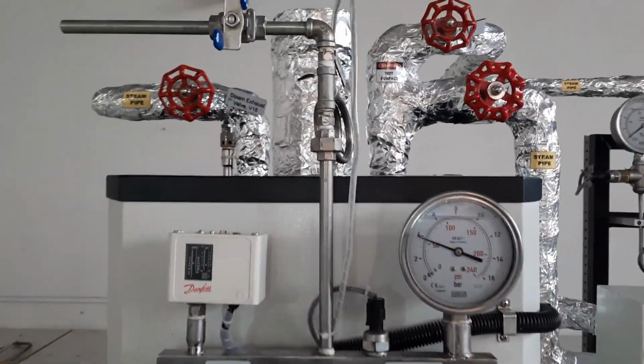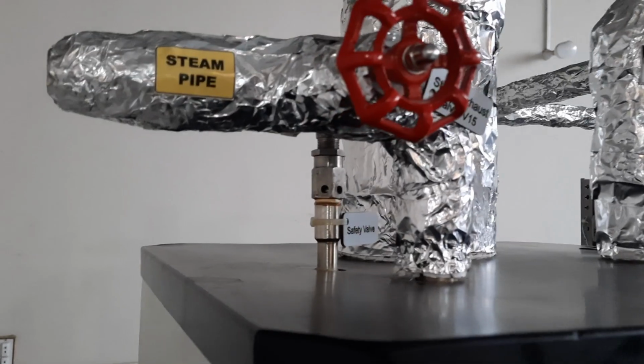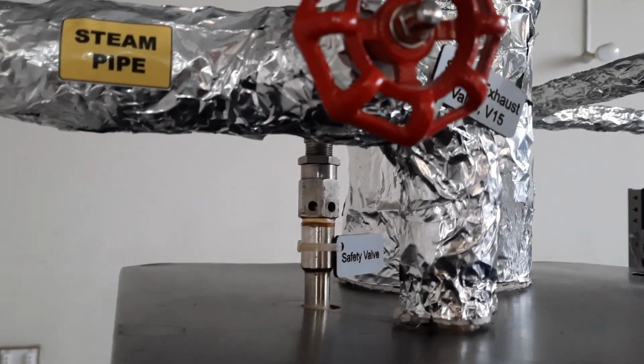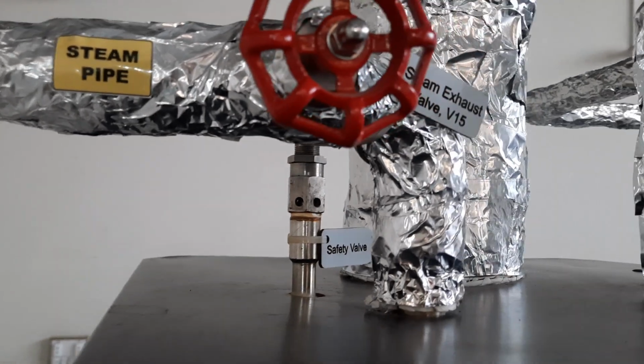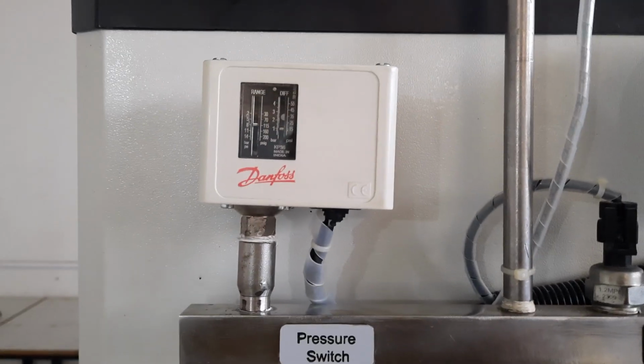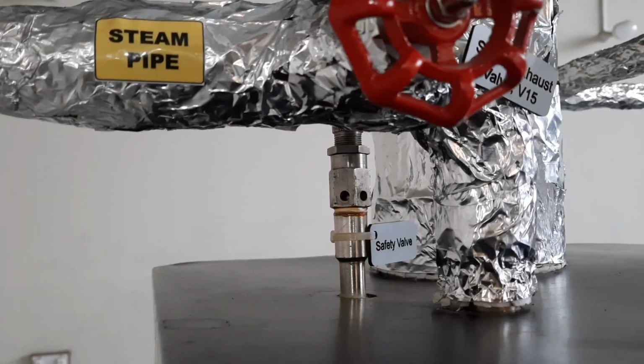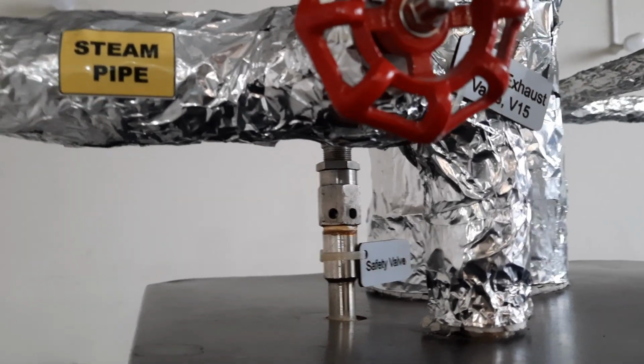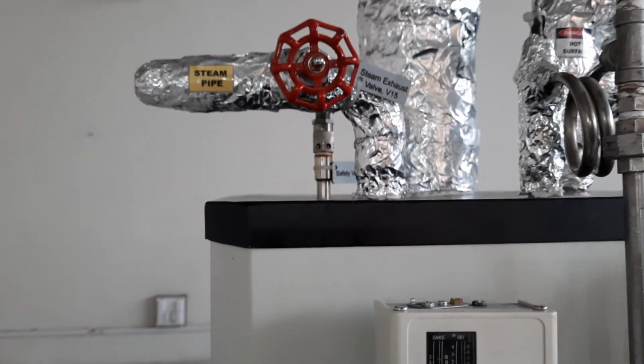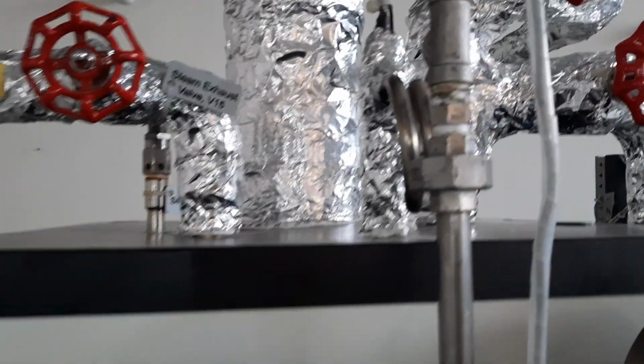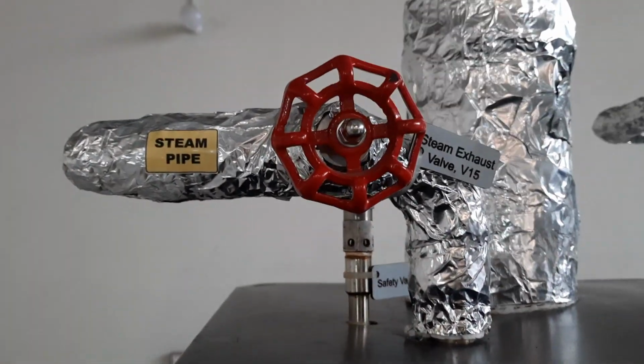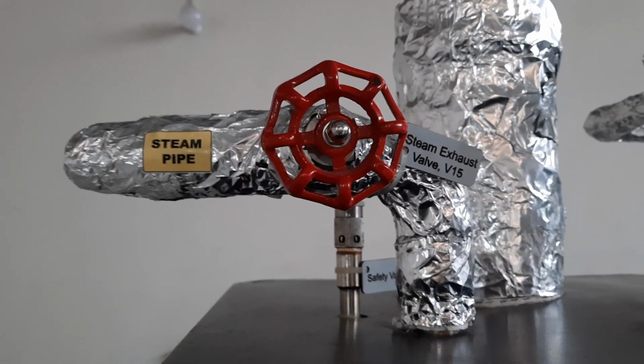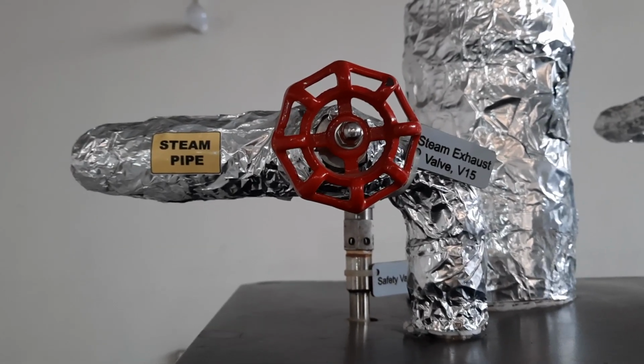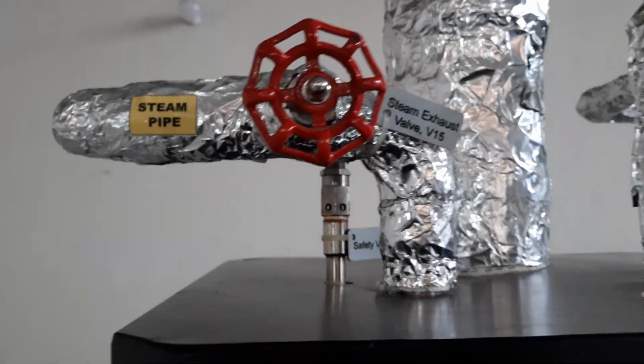At the top of the boiler, this is a safety valve. This is a mechanical safety valve which is set at 8.5 bar. This is the second safety valve. This pressure switch is the first safety valve which trips the boiler at 8 bar, and this mechanical safety valve will start to blow at 8.5 to 9 bar. This valve V15 is the steam exhaust valve which can be used to depressurize the boiler after the experiment.